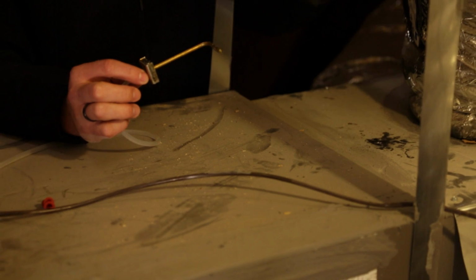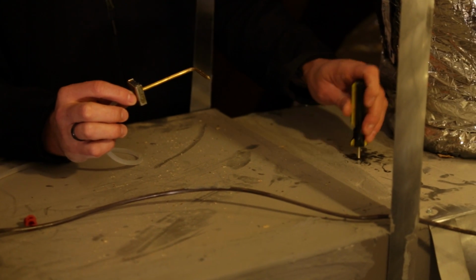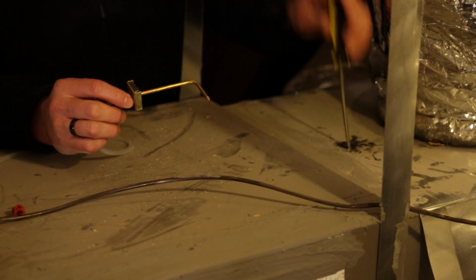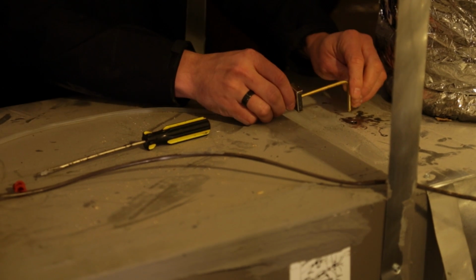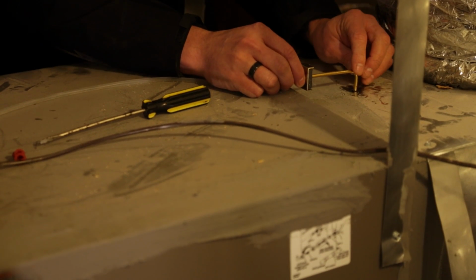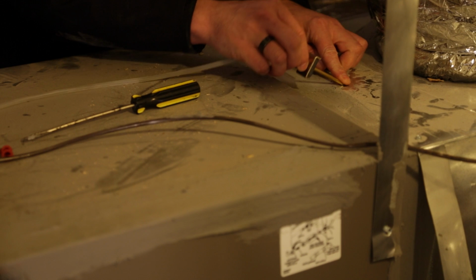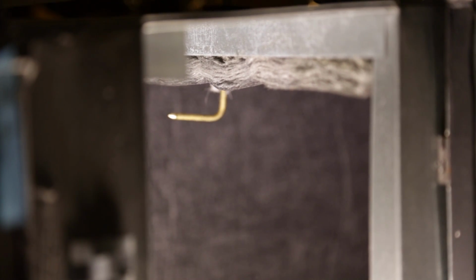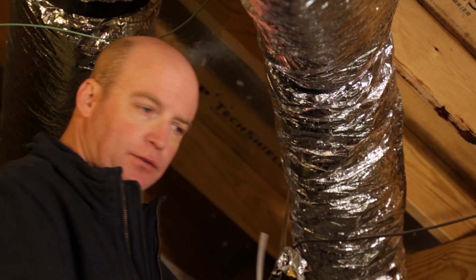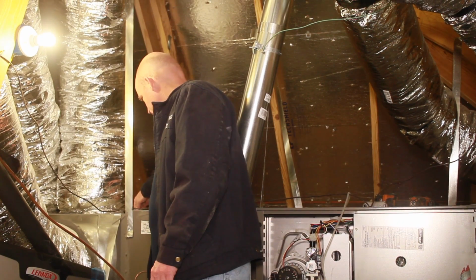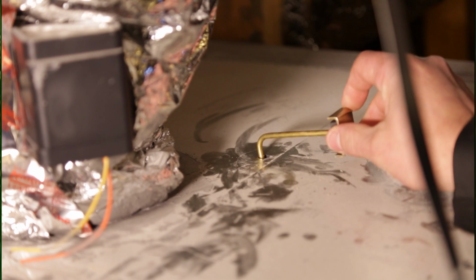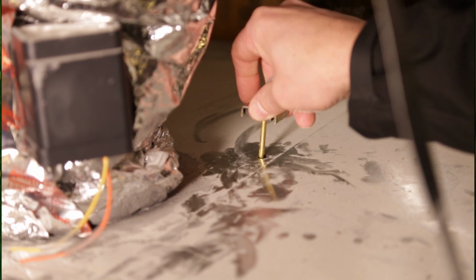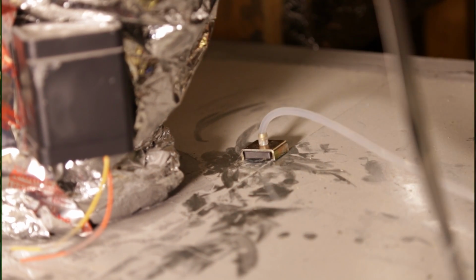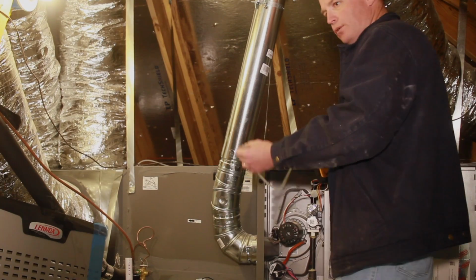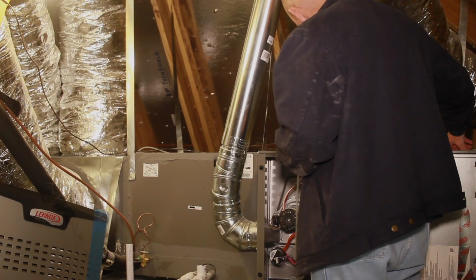We're going to take the probe. Now remember, it is direction specific. The main thing, remember Jacob said, always have them pointing towards you. Since this is on the return side, we're going to have it pointing towards the equipment. Notice, it is not hooked to the meter yet, and I'll show you why in a second. Same thing, we just have to make sure that it goes through the insulation correctly and it's pointed towards the equipment. I have both lines disconnected at this time.